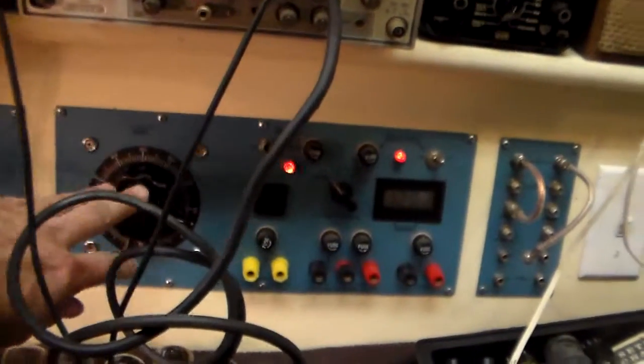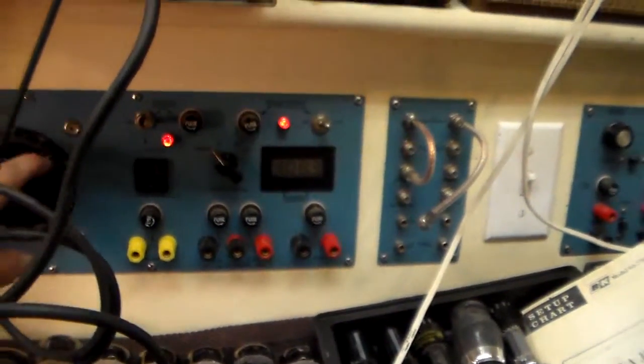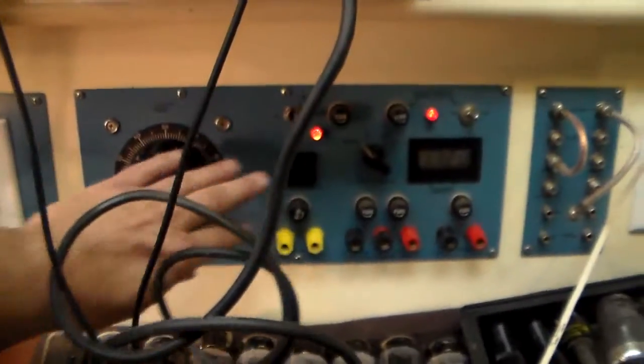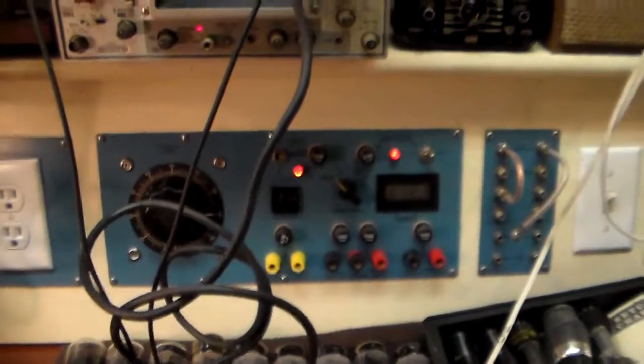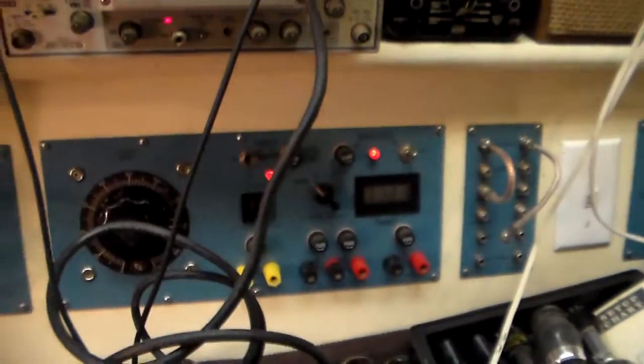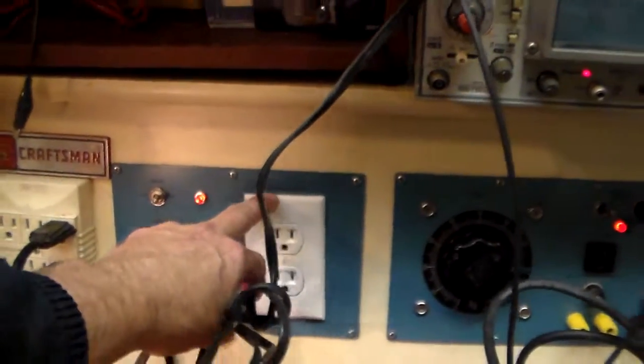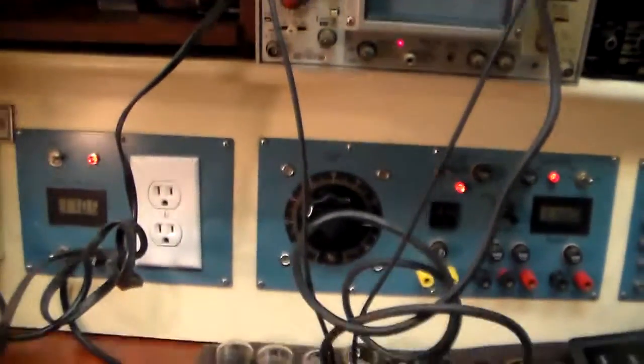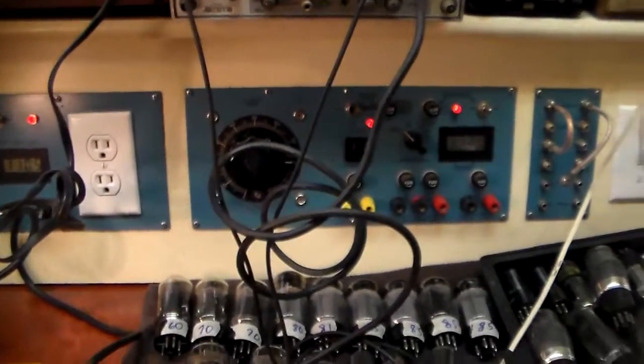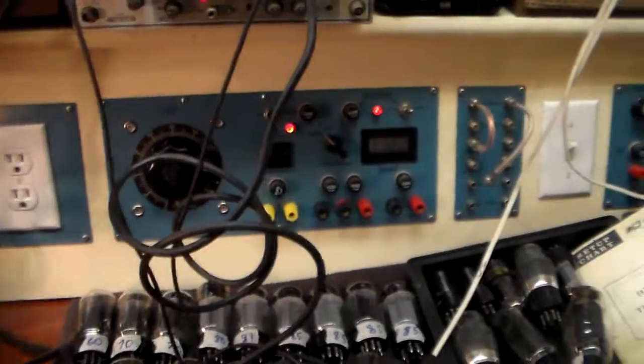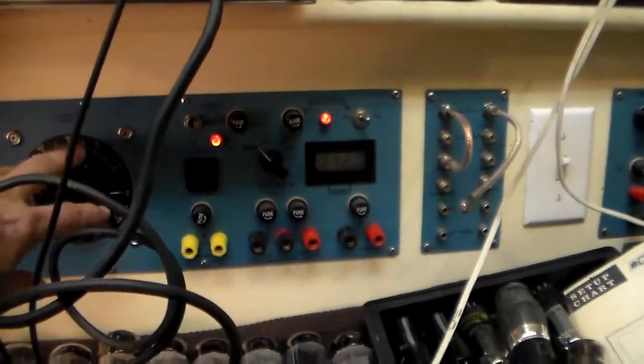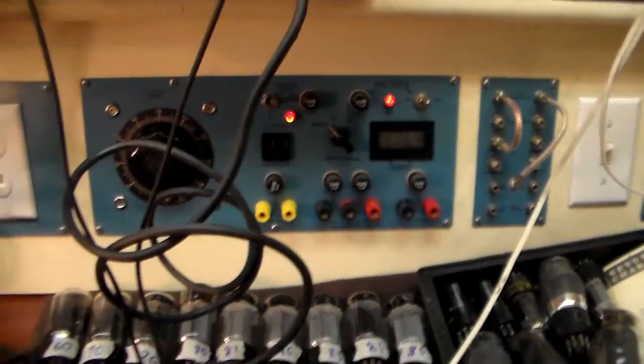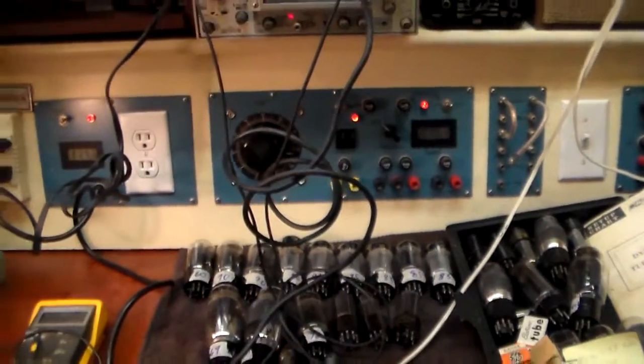This is my variable power supply here. It starts out at zero volts and can run up to 120. So when I start working on these amplifiers I typically plug them in there and switch this over to adjustable which is an isolated power supply which is above ground. I won't get too technical but the guys that work on the equipment know what I'm talking about. And that way I can bring the voltage up slowly to the amplifier and if there's any problems I can see smoke coming out before it does too much damage.